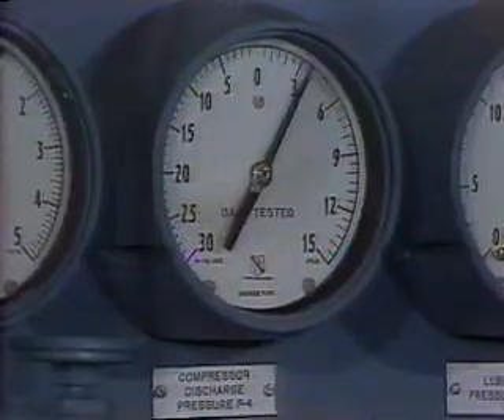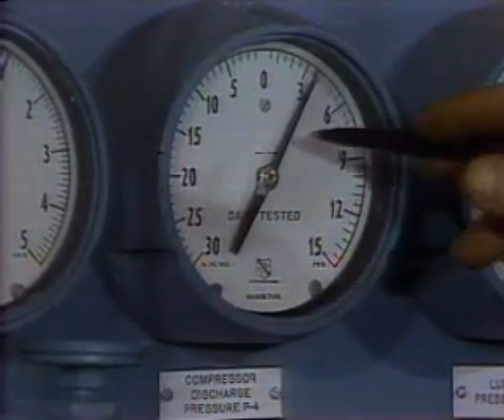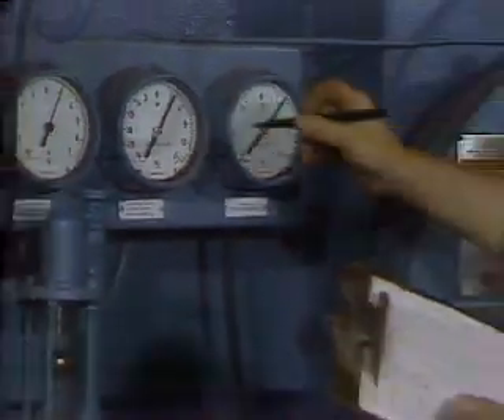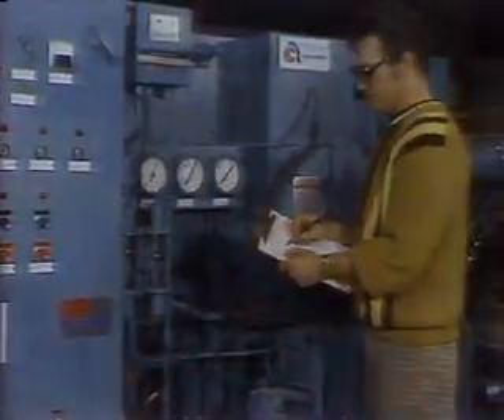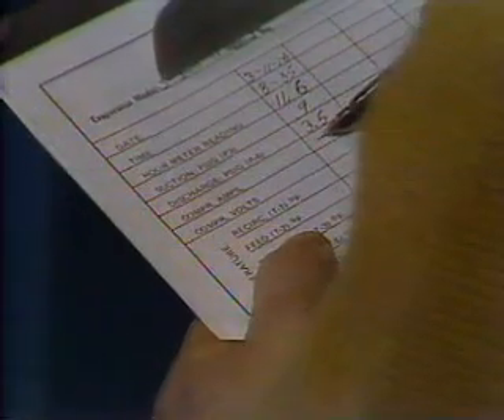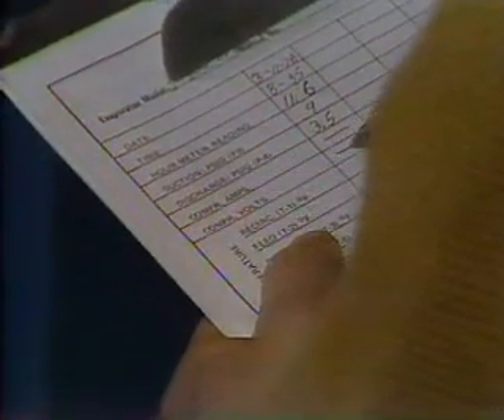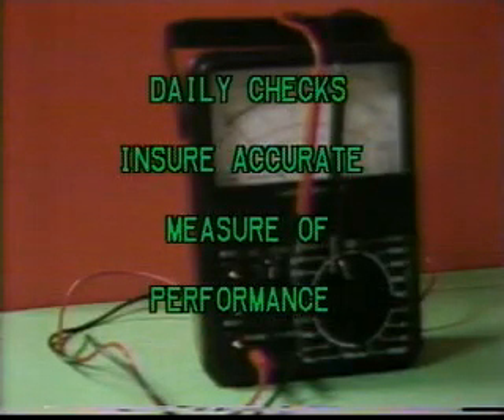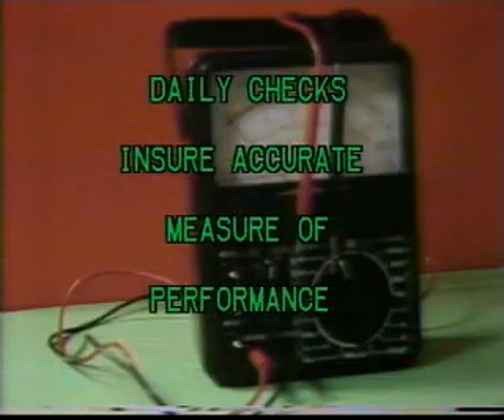Discharge pressure, the second of these three gauges, is logged in the next space. This one is reading 3.5 psig. Compressor amps and voltages should be checked once a week. Many of our operators prefer daily checks as an accurate measure of performance.